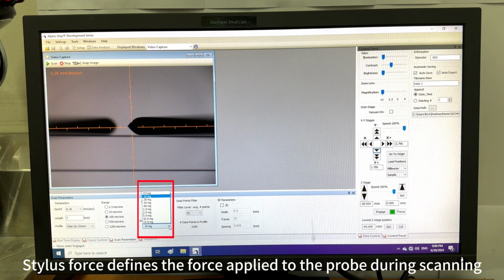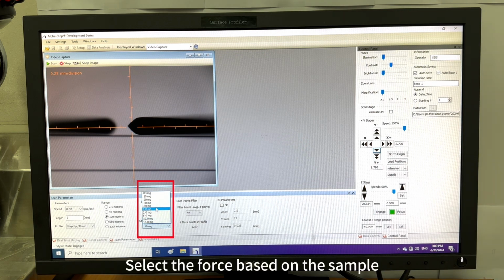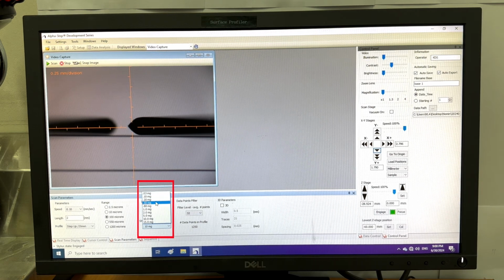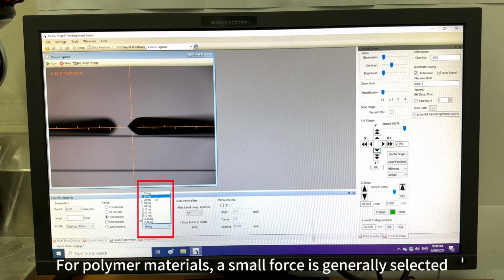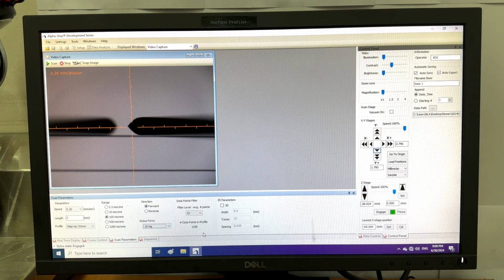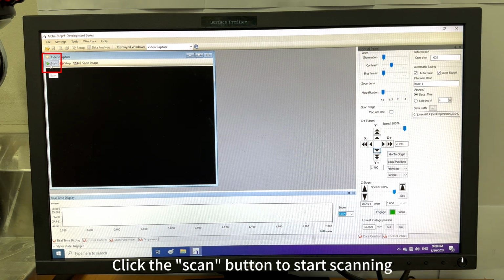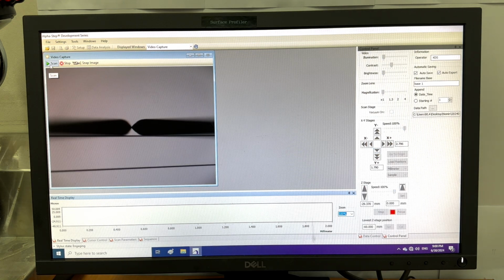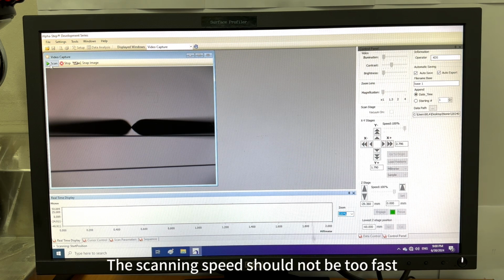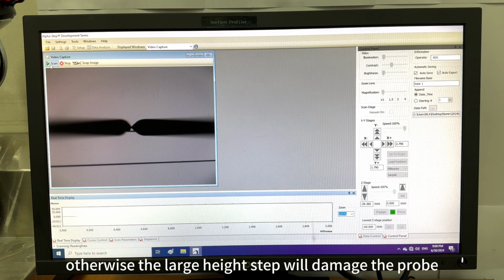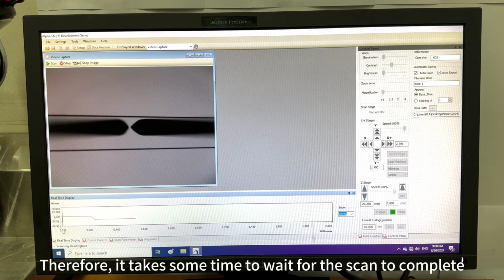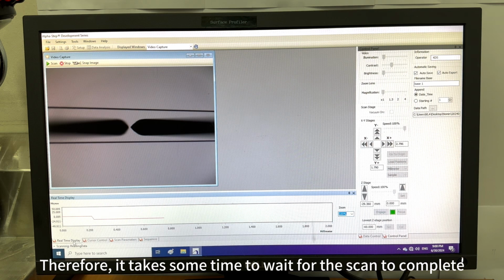Stylus force defines the force applied to the probe during scanning. Select the force based on the sample. For polymer materials, a small force is generally selected. Click the Scan button to start scanning. The scanning speed should not be too fast. Otherwise, the large height step will damage the probe. Therefore, it takes some time to wait for the scan to complete.